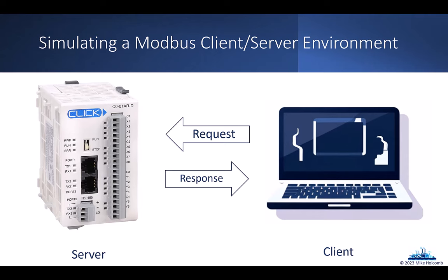And that's where we get into, remember, our key switch. So we want to make sure that we have all of our PLCs in run mode, which this one is not. We can see in the picture, right? Because in run mode, it's read-only. So people can't just manipulate those values remotely and turn a 0 to 1 or a 1 to a 0. Or maybe we turn the 80 degree set point to 100 degrees or 40 degrees. So crank the heat up all the way or crank the air conditioner up all the way. So again, it acts as this client-server where we can issue different requests, right? Read, write, or any of those diagnostics that we have access to.